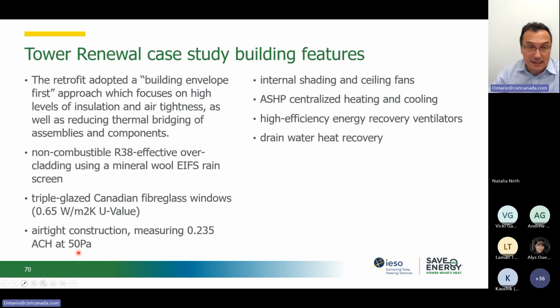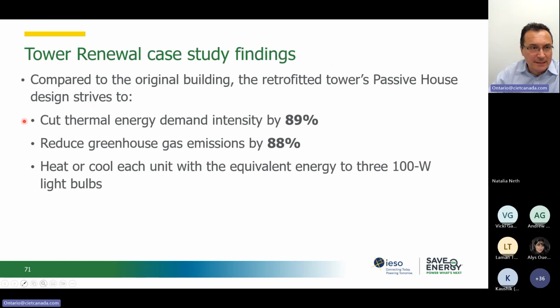This is tremendously low. So in terms of building envelope, and then we used air source heat pumps in addition to this. But again, the loads are much smaller because we dealt with the building envelope first. So as a matter of results, we've seen 89% reduction in the thermal energy demand intensity. This is an indicator that's very popular with this high efficiency performance. So we are looking at the total energy that's associated with the demand, with the heating of the building. So that was reduced by 89%.